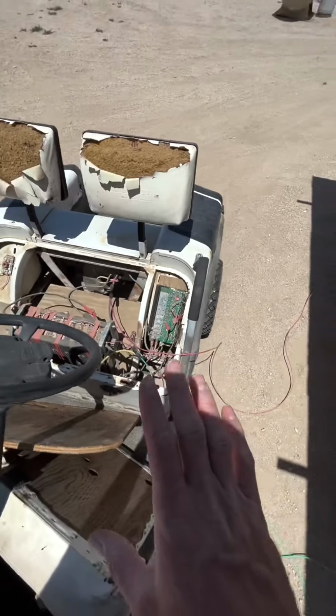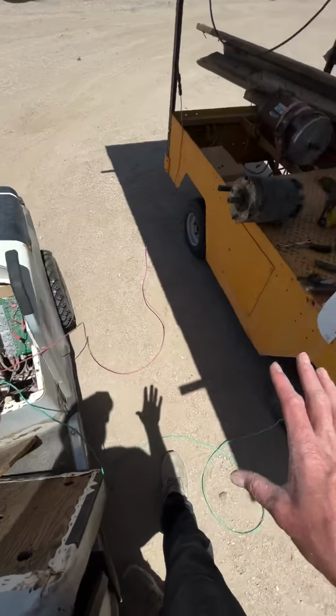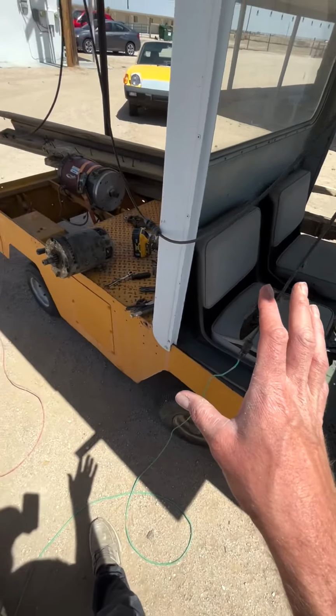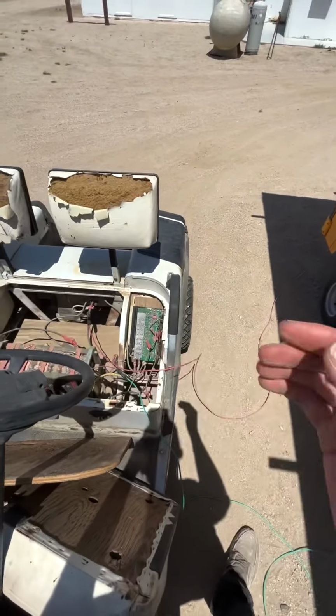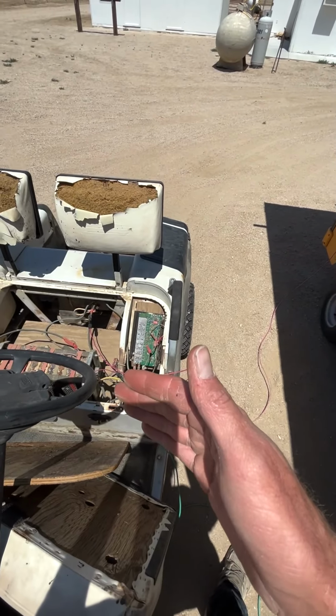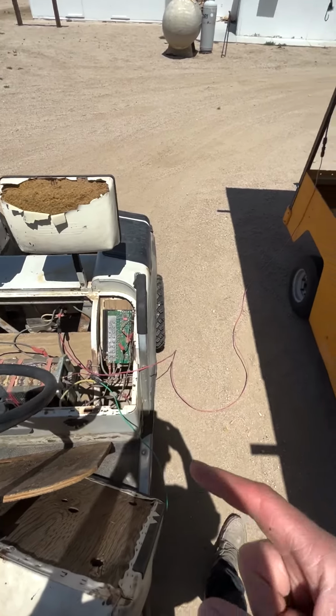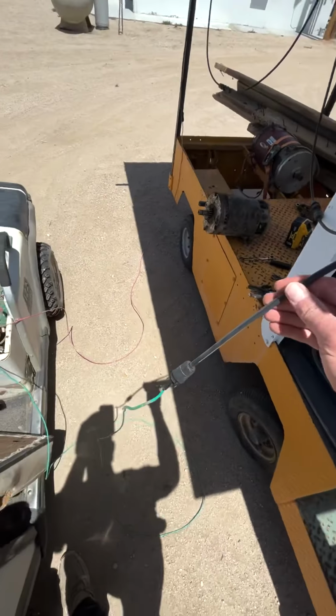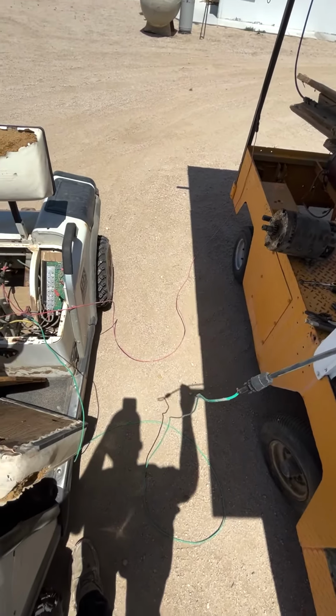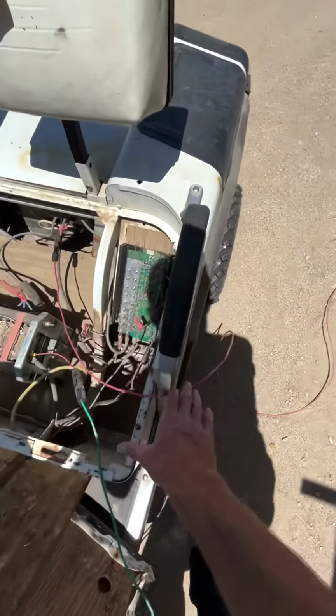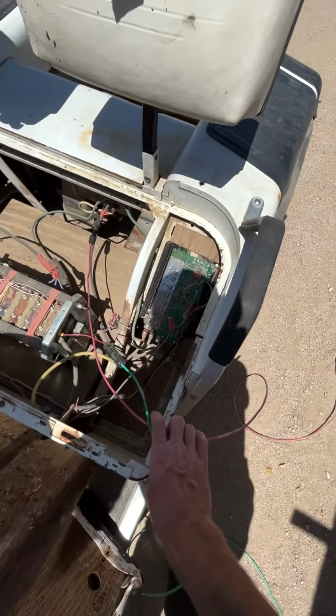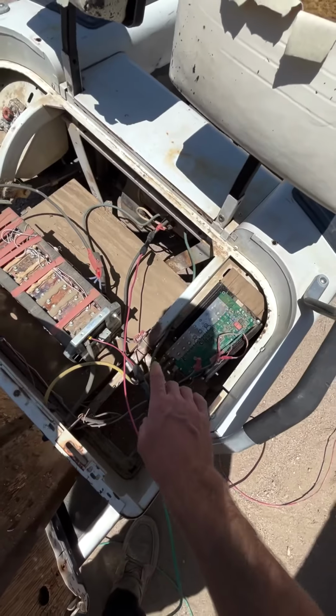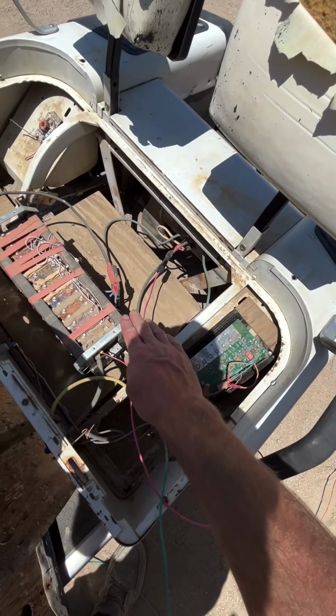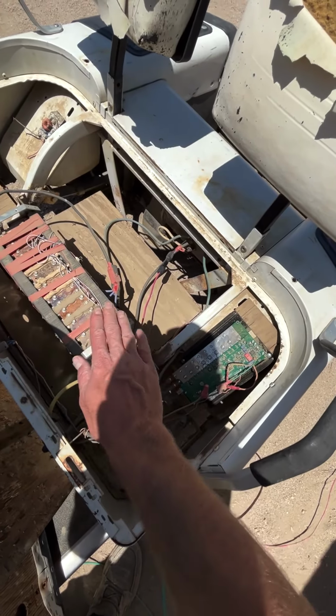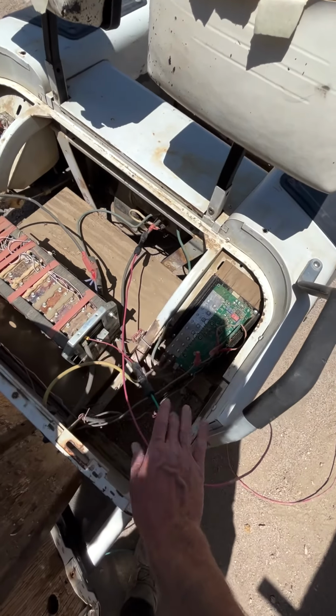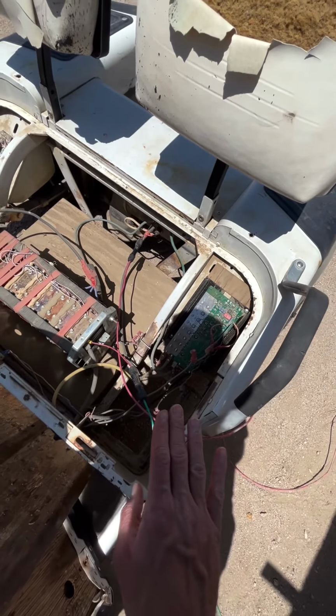The only problem with this solution is if you're doing an off-grid setup and you got a BMS and you're just dumping your power from your panels into your battery, when the battery's full, the solar lines do rise to the open circuit voltage on the panels. So when the charging shuts off, the battery stops taking any power, and the voltage on these lines rises.